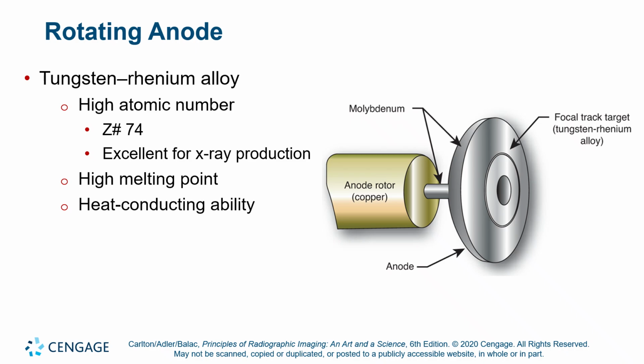So again, what material do we want? Well, it's tungsten rhenium alloy this time. Again, we're choosing tungsten because it has a high atomic number, high melting point, and high heat conductivity. So that means when the tungsten gets hot, it gives away its heat very rapidly, very efficiently.